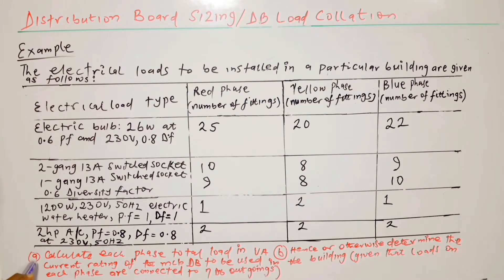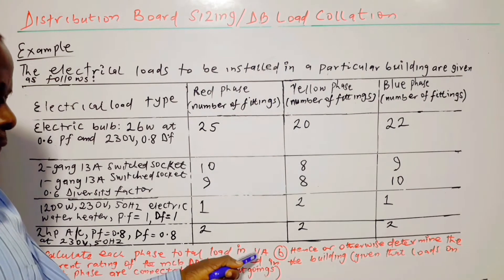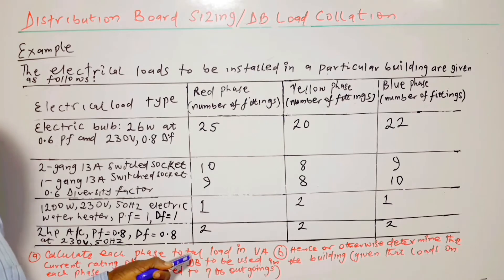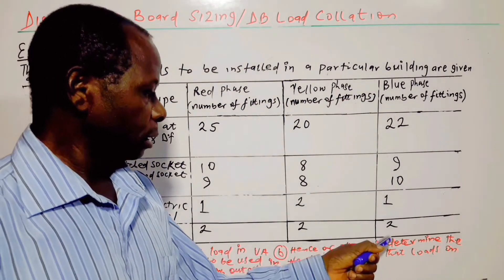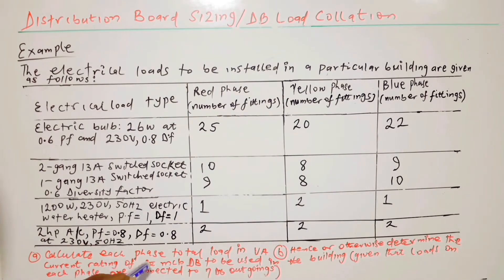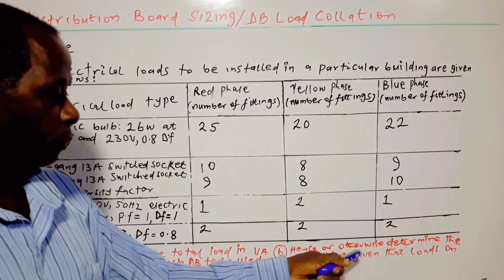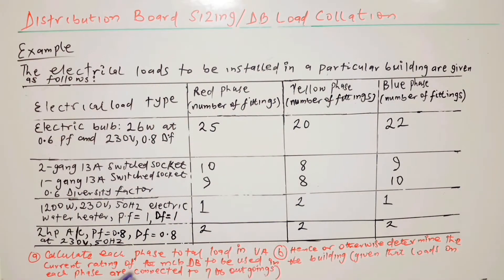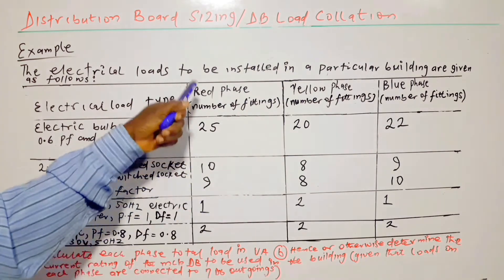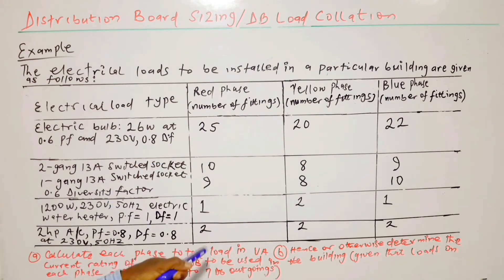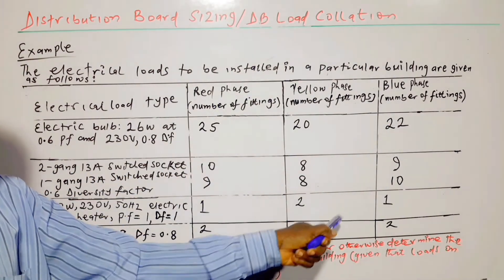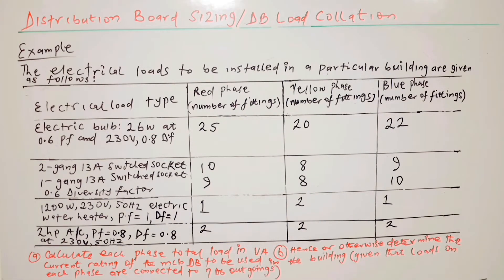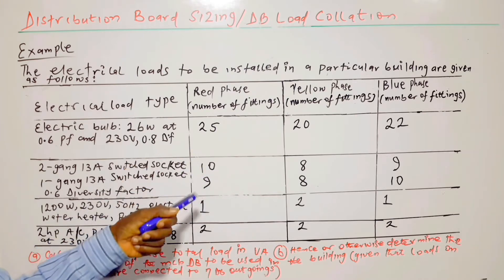Now the questions. Part A: calculate each phase total load in VA — that is the apparent power S on each phase. Part B — hence or otherwise — determine the current rating of the miniature circuit breaker distribution board (MCB DB) to be used in the building. Given that loads on each phase are connected to 7 DB outgoings — 7 for red, 7 for yellow, 7 for blue — giving a total of 21. This is a 3-phase distribution board.